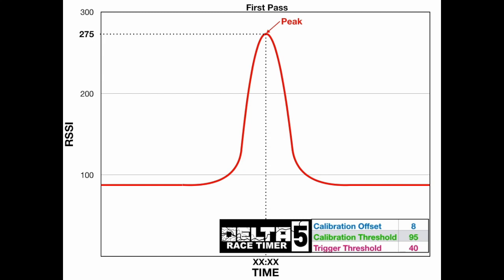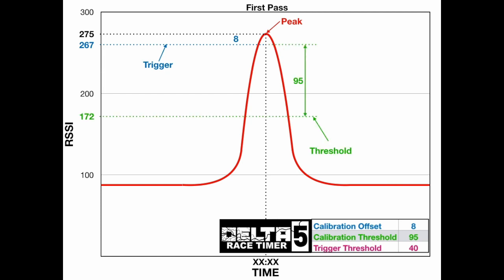Well, first, let's look at the calibration offset, which has a value of 8. The system takes the peak and subtracts the calibration offset and has a value of 267, and that's how it defines the trigger. Now, the calibration threshold is also taken off that trigger line, in this case 95, and establishes a value of 172.